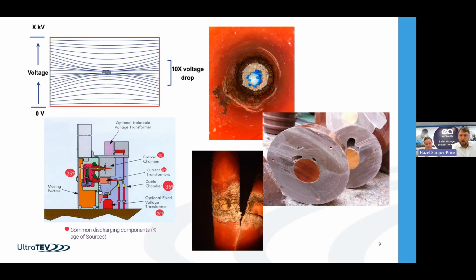In an ideal world, the insulation will be consistent all the way through, and the stress level will be equally divided across that. So when you look at cable termination kits and jointing kits, there are materials in there to manage the change of stress. Any voids are filled with mastics, etc., to avoid any build-up of the electrical stress across a small area.